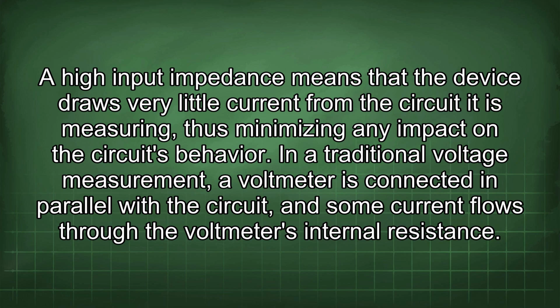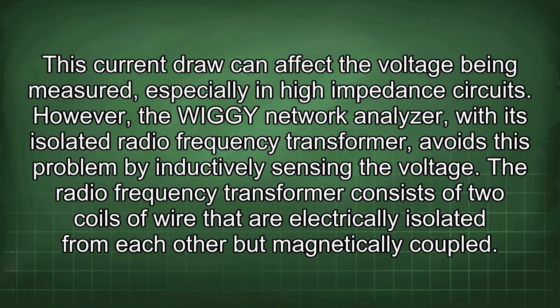In a traditional voltage measurement, a voltmeter is connected in parallel with the circuit, and some current flows through the voltmeter's internal resistance. This current draw could affect the voltage being measured, especially in high impedance circuits. However, the WIGGY network analyzer, with its isolated radio frequency transformer, avoids this problem by inductively sensing the voltage.